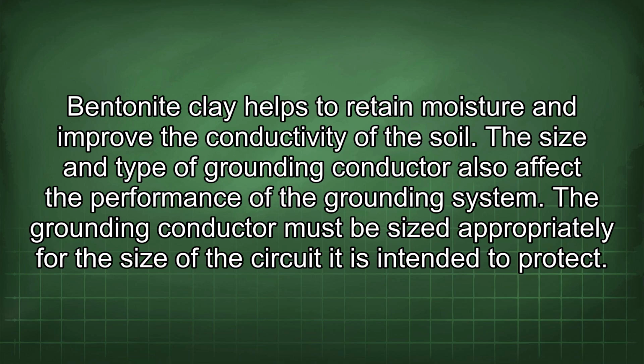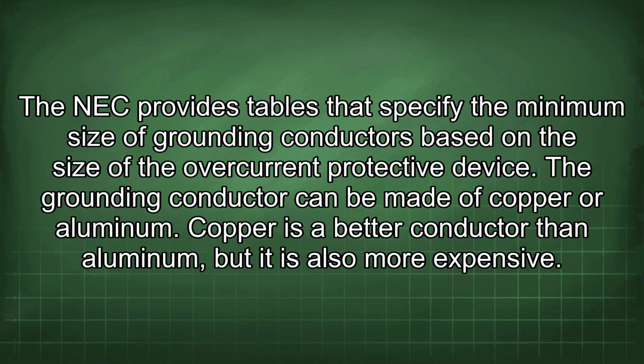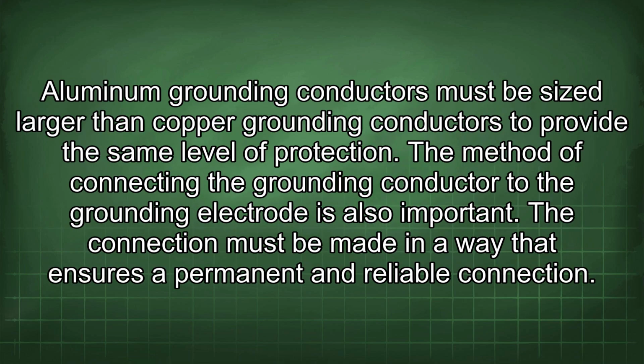The size and type of grounding conductor also affect the performance of the grounding system. The grounding conductor must be sized appropriately for the size of the circuit it is intended to protect. The NEC provides tables that specify the minimum size of grounding conductors based on the size of the overcurrent protective device. The grounding conductor can be made of copper or aluminum. Copper is a better conductor than aluminum, but it is also more expensive. Aluminum grounding conductors must be sized larger than copper grounding conductors to provide the same level of protection.